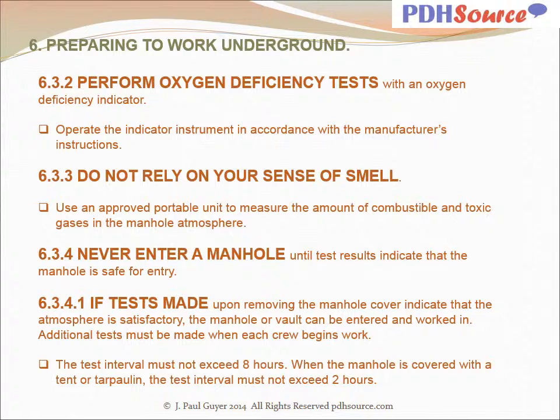If tests made upon removing the manhole cover indicate that the atmosphere is satisfactory, the manhole or vault can be entered and worked in. Additional tests must be made when each crew begins work. The test interval must not exceed 8 hours. When the manhole is covered with a tent or tarpaulin, the test interval must not exceed 2 hours.